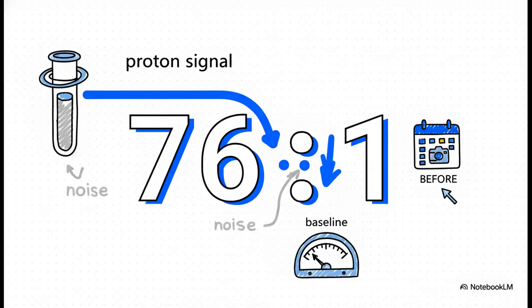So after getting the machine up and running, the engineer runs an initial test on the proton signal, that's the 1H, and the result is a signal-to-noise ratio of 76:1. Now, is that good? Is that bad? Right now it's just a number, but this is our baseline, this is our before picture.